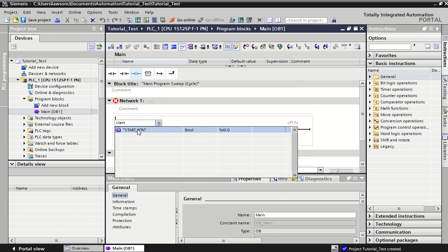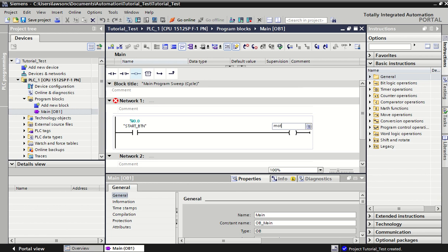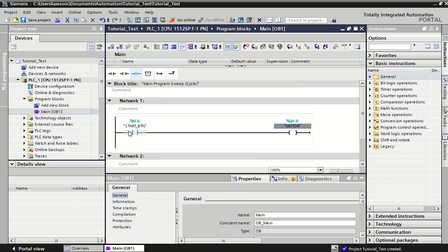Inputs always go on the left-hand side and we can build them up with multiple inputs; outputs go on the right-hand side. When we've dropped them in we can start typing in some code. Because we've already set up our IO, it's very easy to map them in — we don't have to keep entering those addresses again. We've given each signal a tag name that we can call very easily. So in this first line of code, when we push the start button our motor becomes energized — power flows through and energizes the coil, turning on our motor.